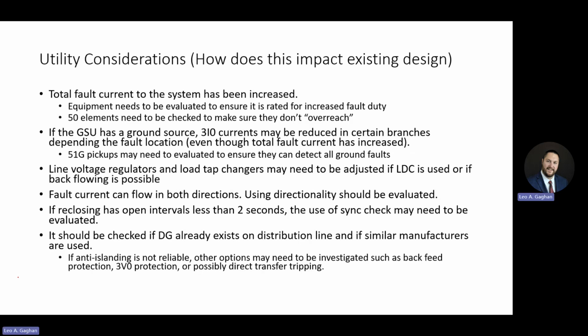So, some utility considerations out of these inverter-based resources, these renewable generation sites: how do they affect things? We are adding to the fault duty of the system. Maybe we had a system with 5,000 amps. Now the fault duty may be 6,000 amps. Studies need to be done to ensure that the equipment on that system can handle that increased fault magnitude. Things like breakers, switches, damage curves on transformers, and cables, overhead conductors, bushings. All of these things can only handle so much fault current, so those need to be looked at.